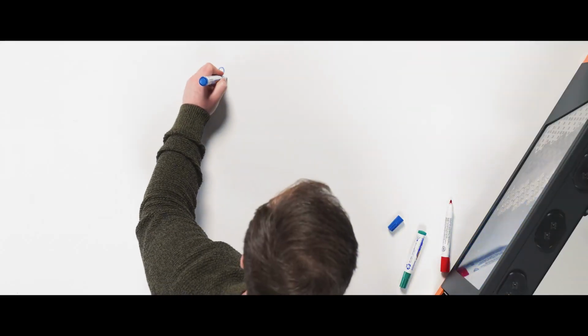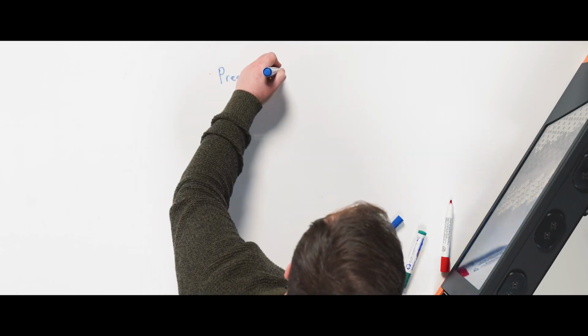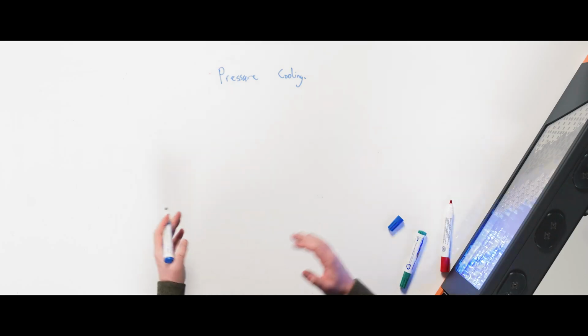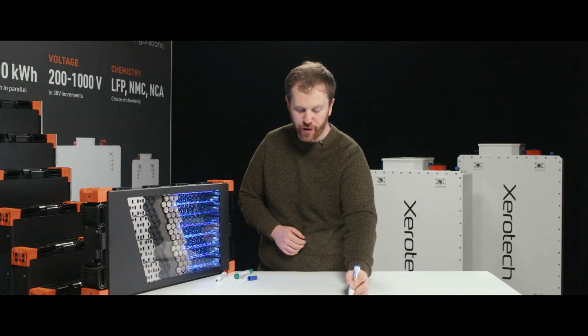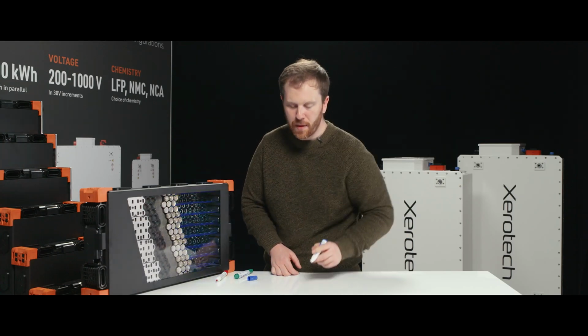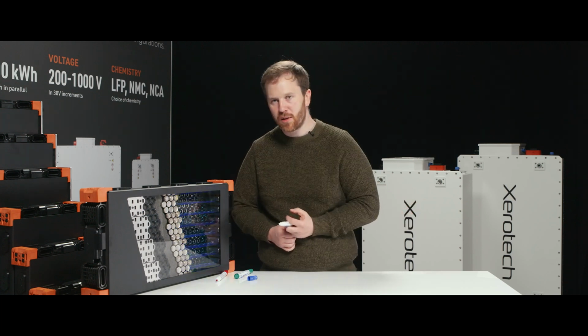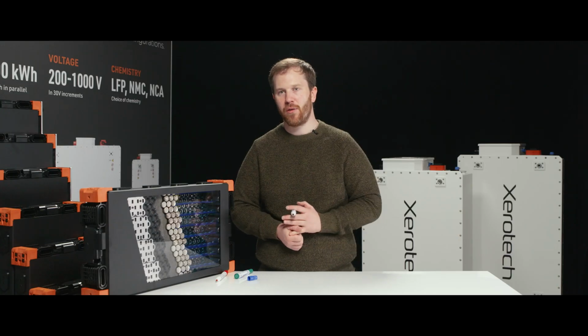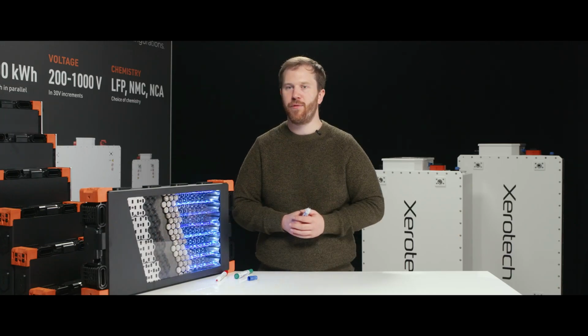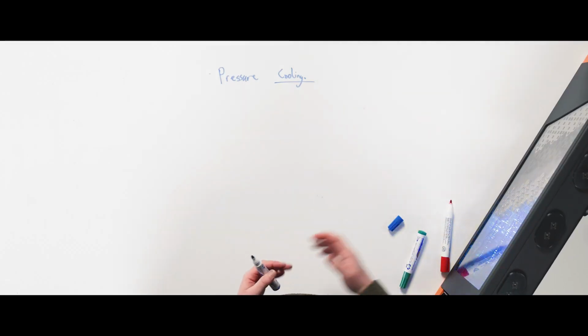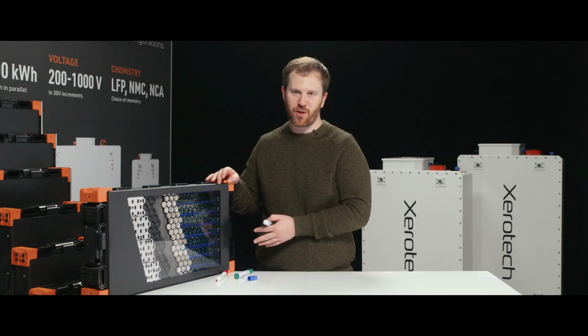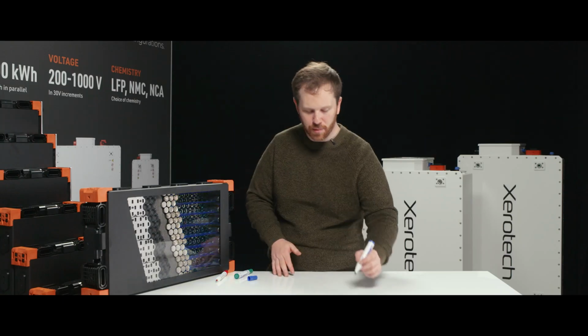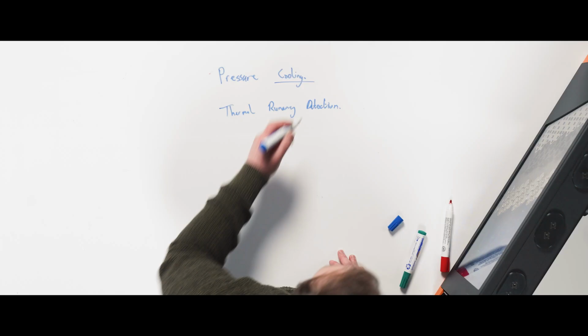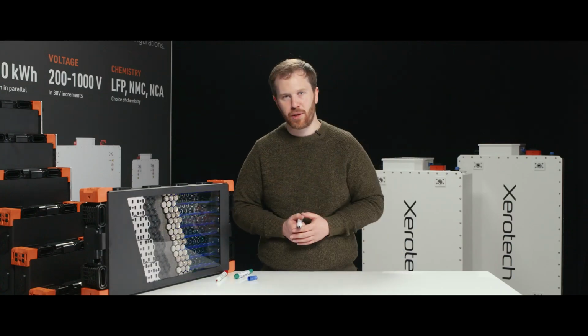When it comes to other system level safety measurements, this varies very widely from pack supplier to pack supplier. So we'll just take the case of a Xerotech battery. We do also monitor other factors, such as the pressure in the cooling system to determine if there's leaks or failures, and we use this for second and third level protection, also to infer other ways that the system is being used. And also we will be looking at pressures inside of the housing and gas sensing and other factors as well to be early indicators or detections of thermal runaway. So thermal runaway detection is very, very important, that if something occurs in a battery, you want to know what's happened. Oftentimes there's very little pack manufacturers can do after it's happened, but detecting it is the first step. So thermal runaway detection. And as part of multi-layered safety within our pack, for example, we have multiple different detection methods to see what happens.